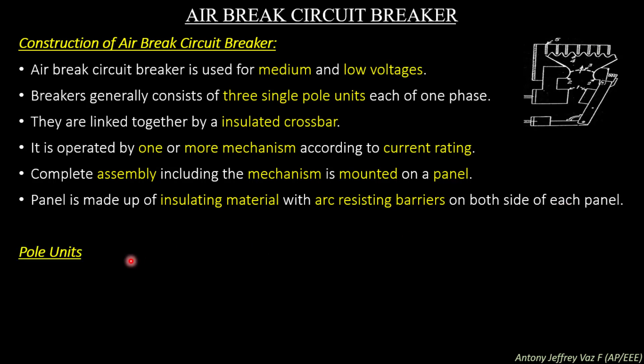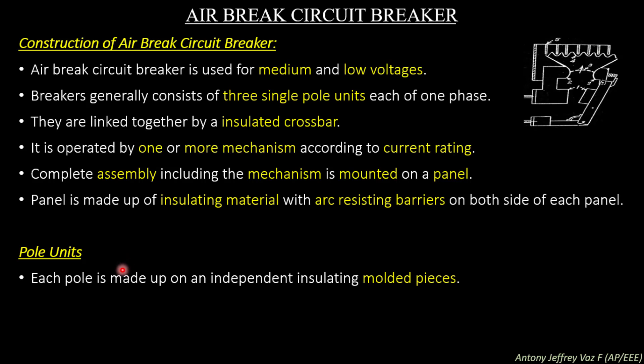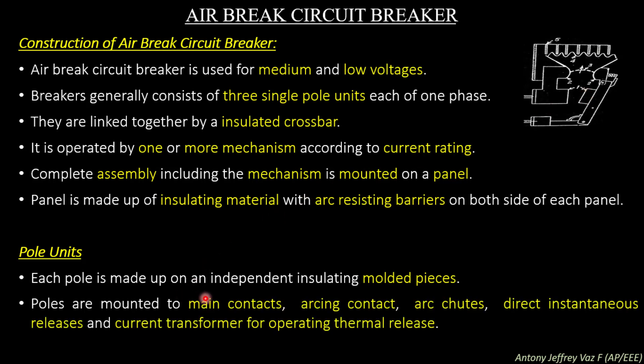Each pole is made up of independent insulating molded pieces. The pole units represent the contact parts and these two contact parts of an air break circuit breaker are connected with insulated material of very high dielectric strength. The poles are mounted with main contacts, arcing contacts, arc chutes, direct instantaneous release, and a current transformer for operating thermal release.